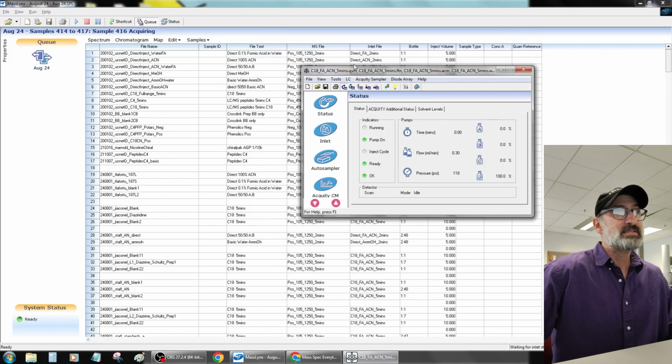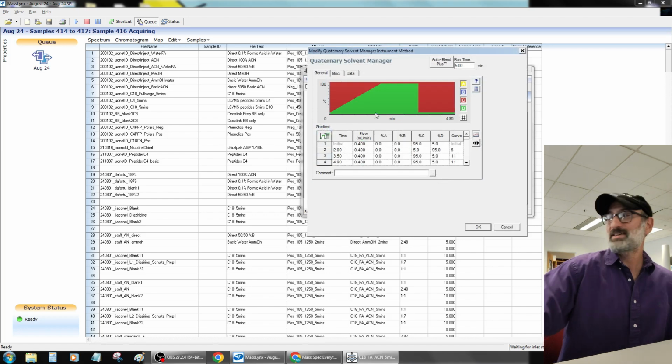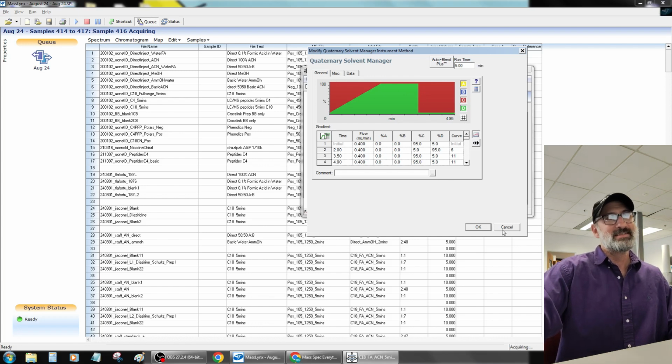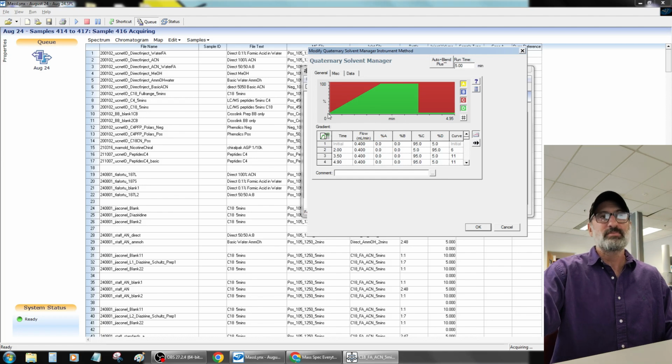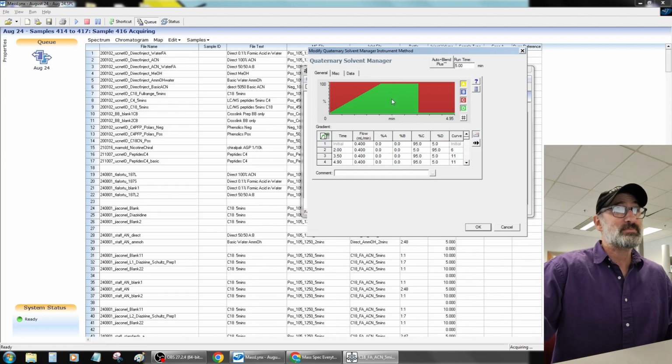Okay, so this is my C18 method, and this is the way my generic C18 method looks. It's as blocky as you could possibly get. It's just straight up, then up to 95%, and then drops off a cliff and equilibrates itself. You can do way better than this. This is a really, really rookie gradient. A lot of times I'd like to run it out at like 3% B and get it to really stick to the column for half a minute, and then go up nice and then come back down nicely as well, not just a step off a cliff. But if you're doing quick and dirty, this is a good one. This is what we've been running. You could do better than this, but...